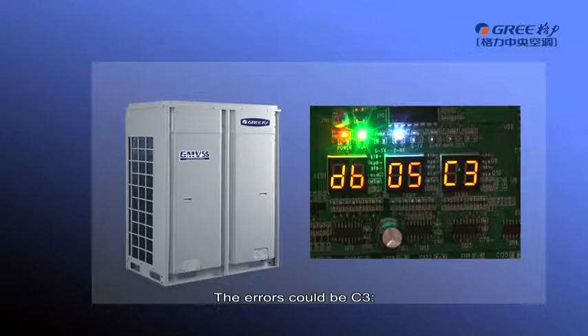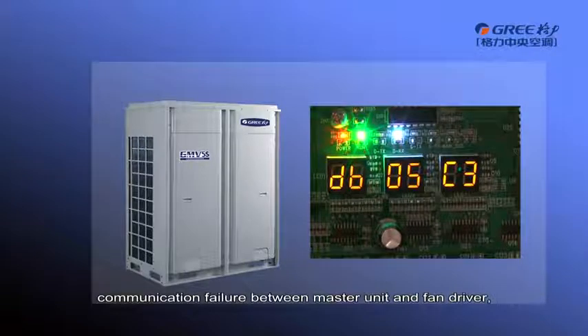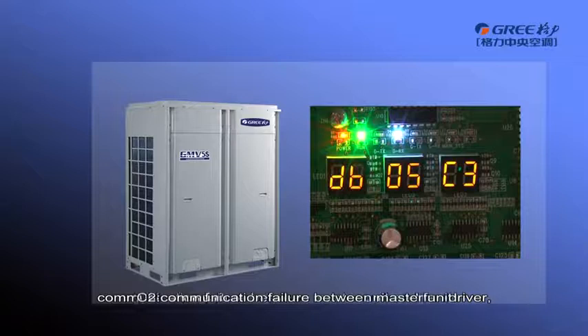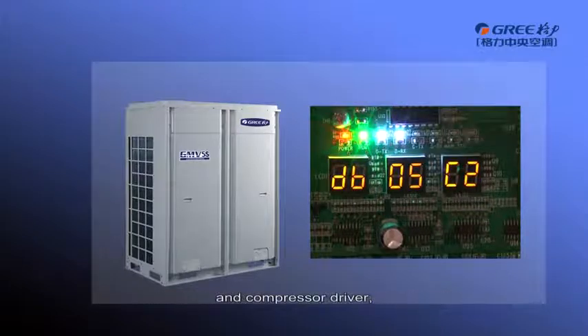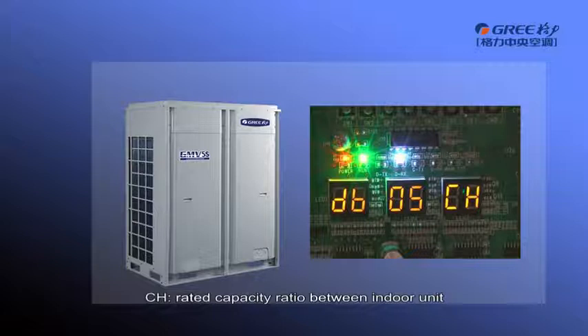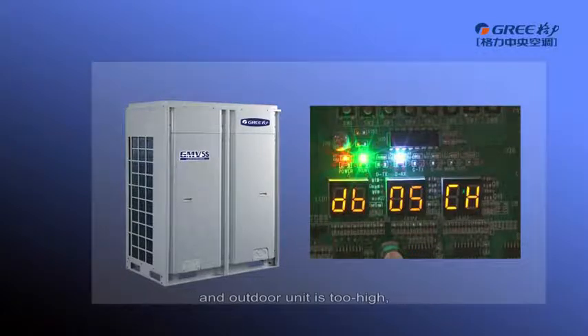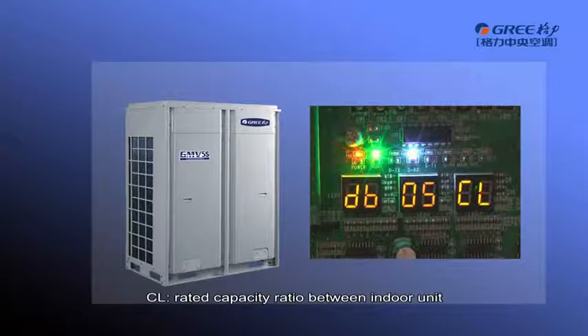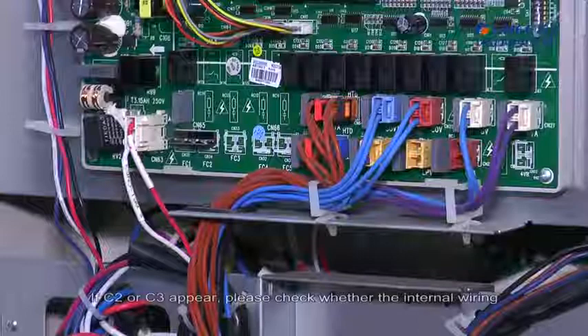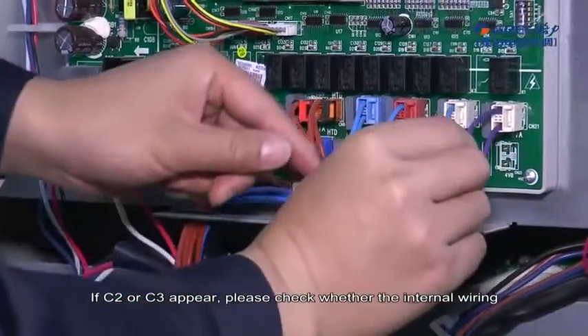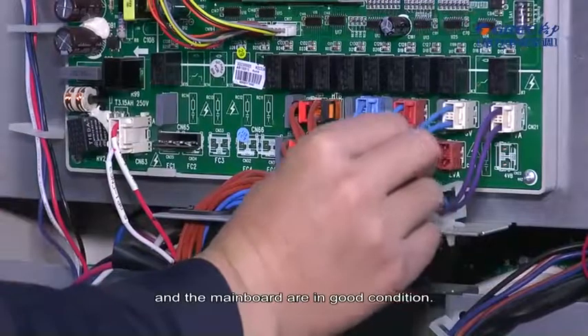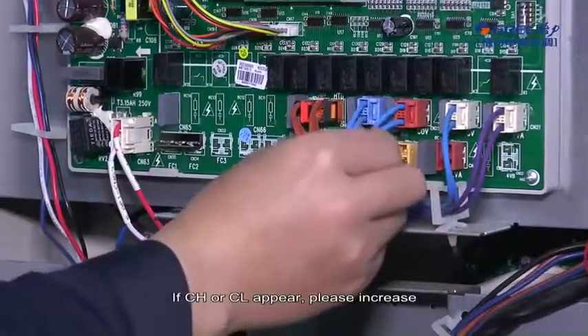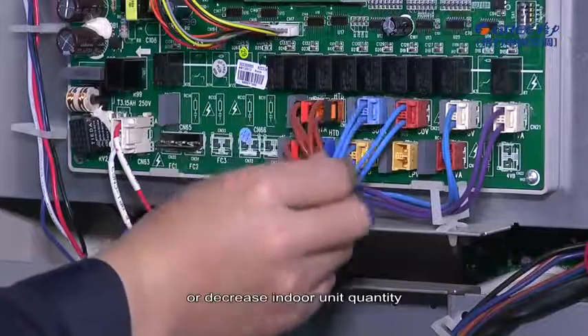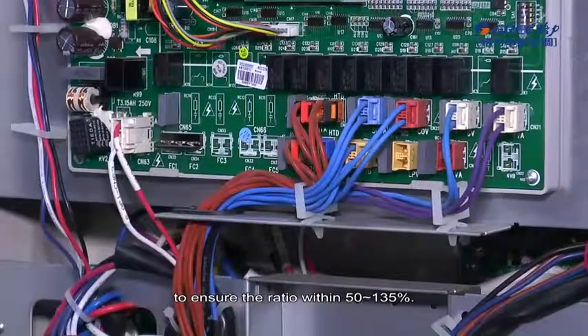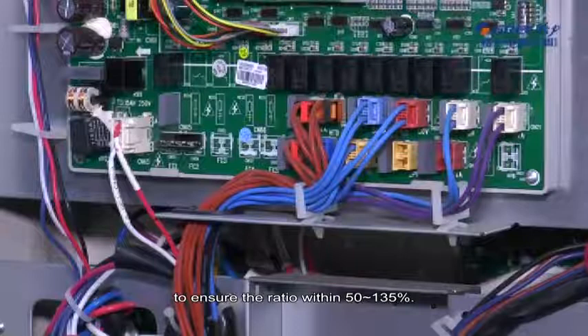The errors could be C3, communication failure between master unit and fan driver. C2, communication failure between master unit and compressor driver. CH, rated capacity ratio between indoor unit and outdoor unit is too high. CL, rated capacity ratio between indoor unit and outdoor unit is too low. If C2 or C3 appear, please check whether the internal wiring and the mainboard are in good condition. If CH or CL appear, please increase or decrease indoor unit quantity to ensure the ratio within 50 to 135%.